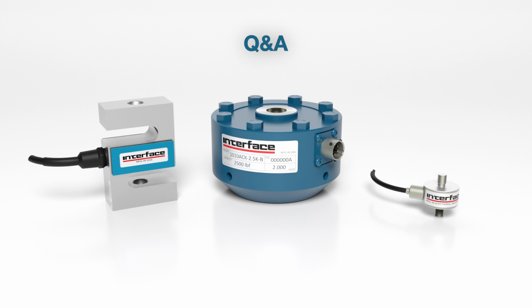Can you explain why WMS does not need a jam nut versus low profile does? Sure, I can answer that. It has to do primarily with how you're introducing the load into the load cell. With a low profile, being a shear beam design, the gauges are at a similar height, if you will, as to where the threads are in the flexure. So the whole point of using a jam nut on an LP is to preload those threads. So you're going to introduce the load not through specific threads, if you weren't tight, but through the hub face and also a consistent point in the flexure itself.